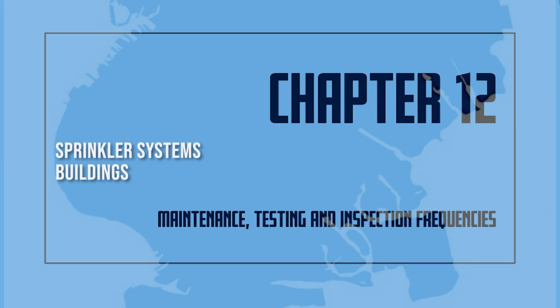Buildings. Annually, prior to freezing weather, buildings with wet pipe systems shall be inspected to verify that windows, skylights, door ventilators, other openings and closures, blind spaces, unused attics, stair towers, roof houses, and low spaces under buildings do not expose water-filled sprinkler piping to freezing, and to verify adequate heat with a minimum temperature of 40 degrees Fahrenheit.